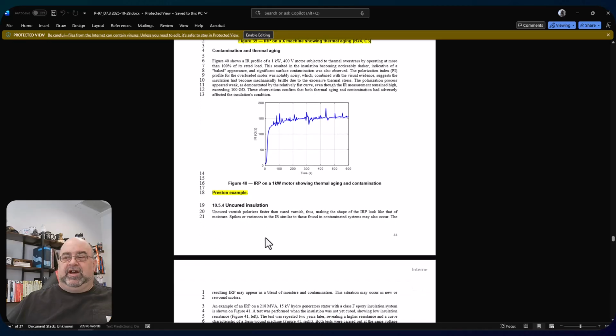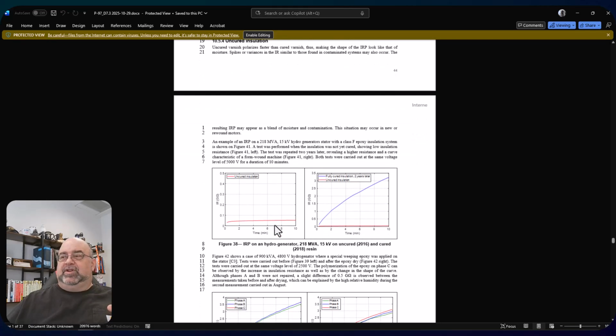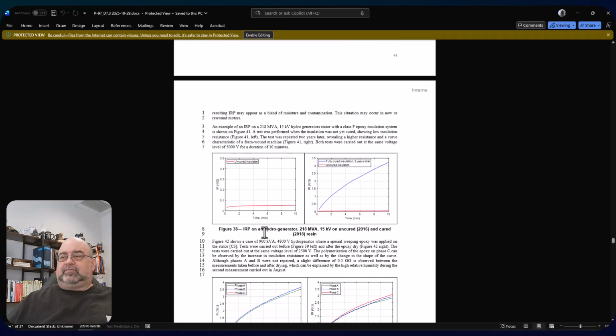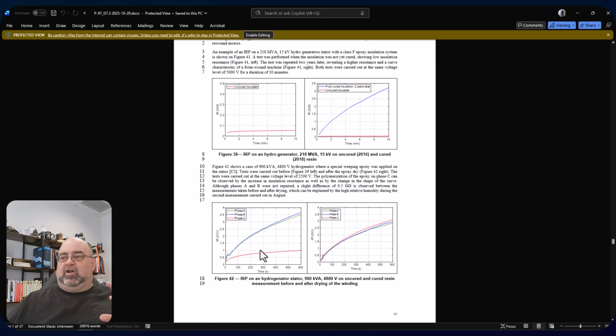Here's an uncured versus cured example. This was a larger one. This is a smaller hydro generator, in which you can see one curve is quite low. That is the insulation where we actually put, this is mine as well, a special type of liquid insulation in there that's a penetrant. It's supposed to fill in all cracks and stuff on an aging insulation system.